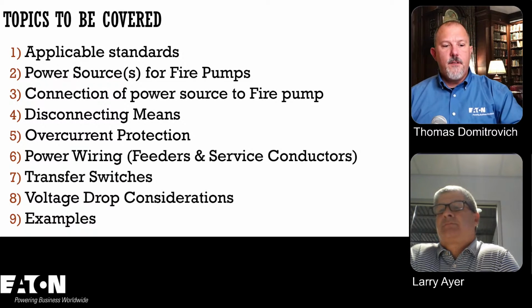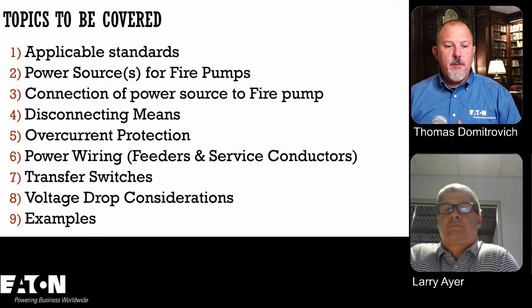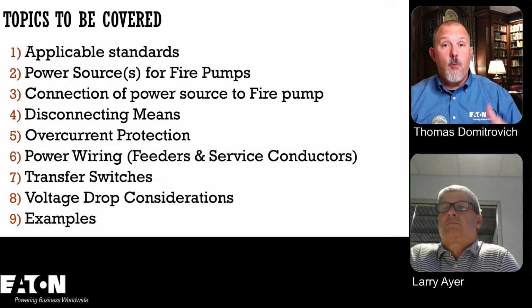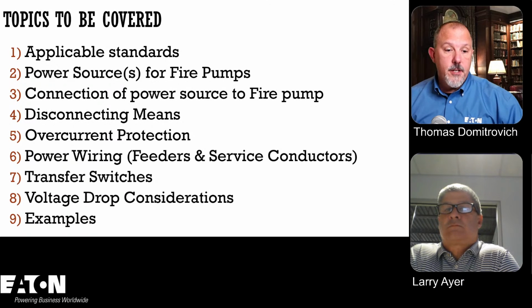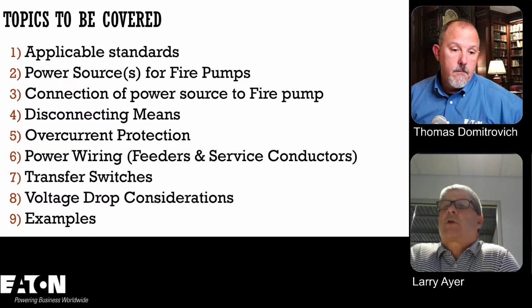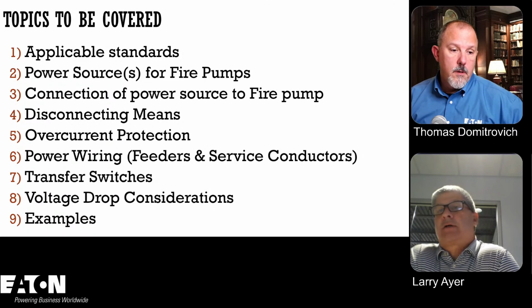Yeah. And Felix pointed out, he's like, is that fire pump, a jockey pump room, considered a wet location? I wouldn't consider it a wet location. Just because you have water pipes there, I would say that is not a wet location. Correct. Yeah, I would not consider it a wet location.